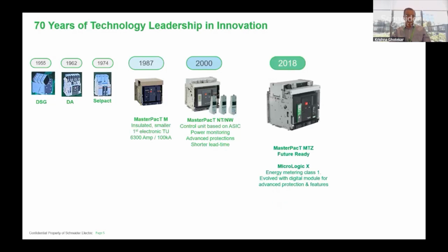Fast forward around 1.5 decades later, we upgraded and brought to the market another MasterPact MTZ with MicroLogic X type of trip unit. Now this one was with very high features because in the last 5 to 10 years, 7 or 8 years, digitization is getting picked up very quickly. Whether you talk about data centers or even our homes, most of the things are digitized. So that's why we added more digitization into our traditional circuit breakers, which sit in the LV panels. MTZ-X came with class 1 accuracy energy metering, and multiple advanced protections were put into it, which can be added digitally. So you can upload the software, and the breaker is ready for the next protection. It has mobile applications where you can easily connect with Bluetooth, NFC, and other features.